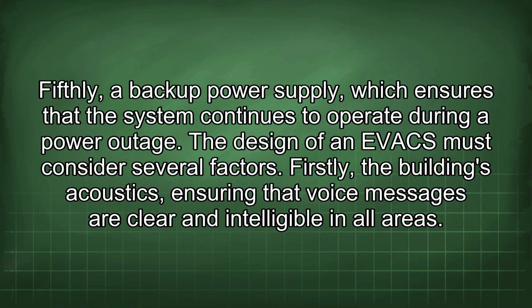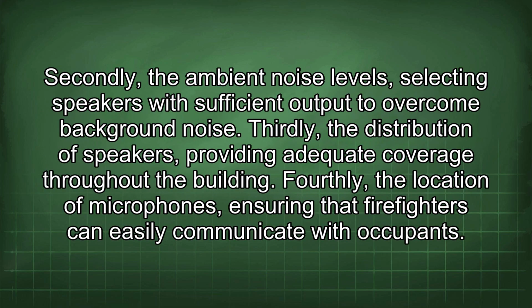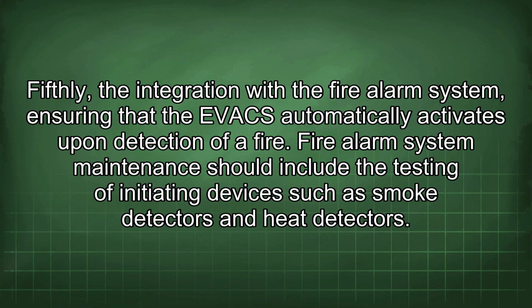The design of an EVAC must consider several factors. Firstly, the building's acoustics, ensuring that voice messages are clear and intelligible in all areas. Secondly, the ambient noise levels, selecting speakers with sufficient output to overcome background noise. Thirdly, the distribution of speakers, providing adequate coverage throughout the building. Fourthly, the location of microphones, ensuring that firefighters can easily communicate with occupants. Fifthly, the integration with the fire alarm system, ensuring that the EVAC automatically activates upon detection of a fire.